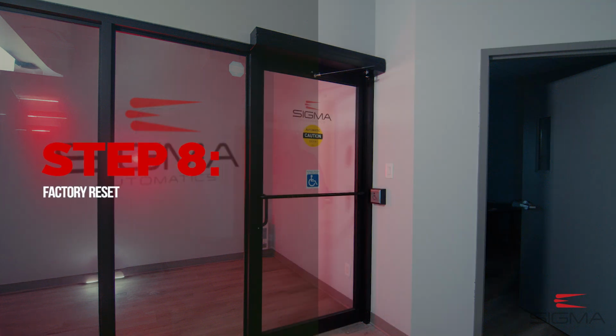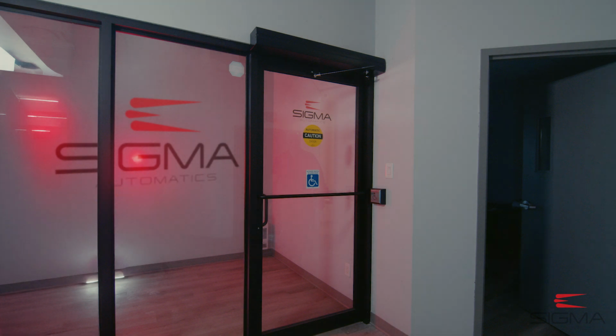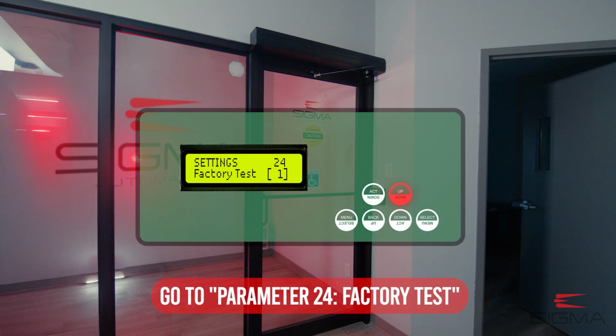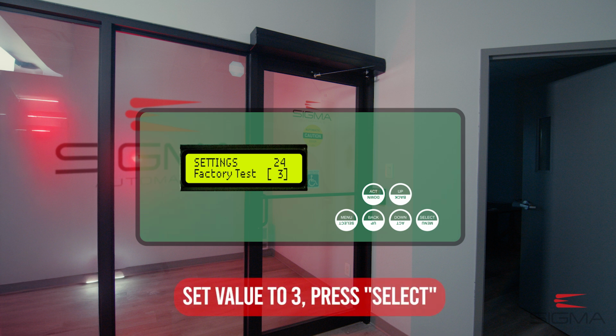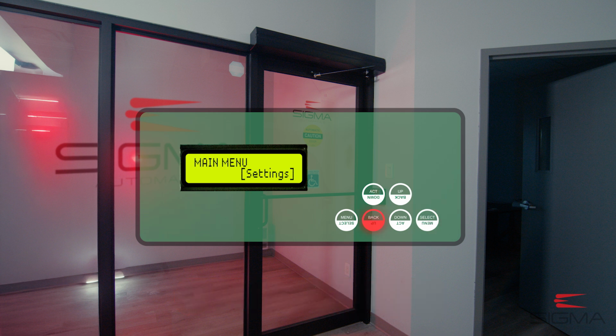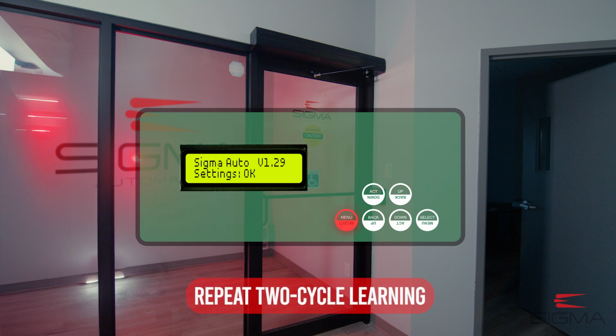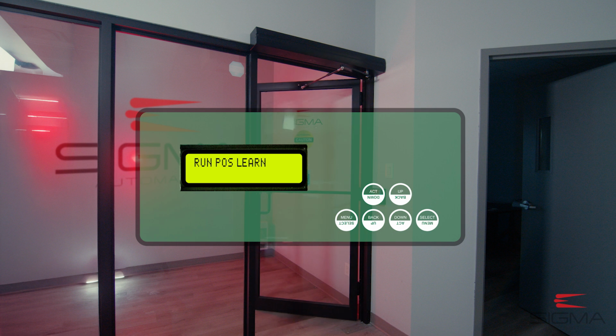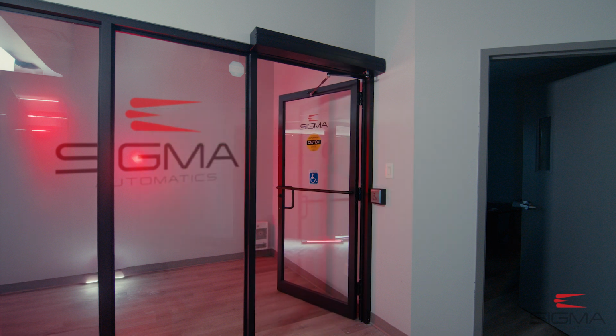If at any point you need to reset the operator, simply navigate to Parameter 24, Factory Test. In the menu, change the value from 0 to 3 and press Select, then press Back, and then Menu. The door will rerun its checks and return to its original setup. Repeat the 2-cycle learning process as you did during the initial setup.